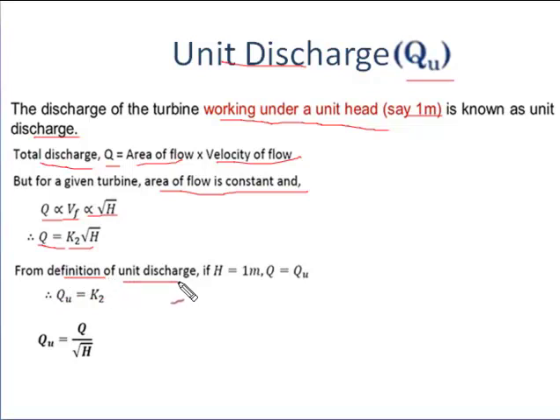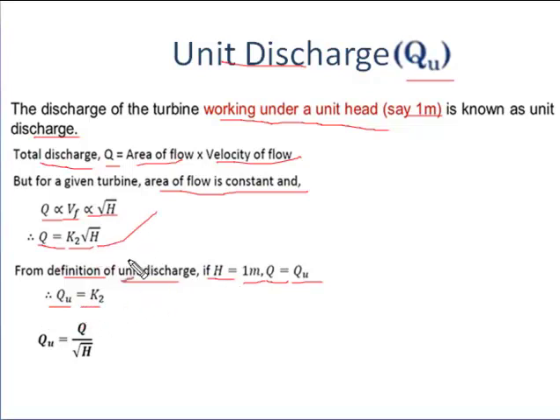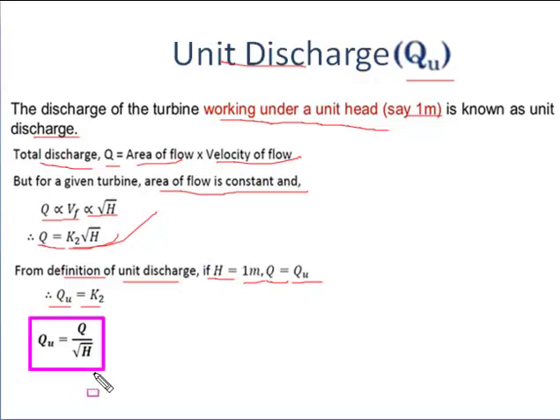Taking the proportionality constant, we get Q = K₂·√H. From the definition of unit discharge, if H = 1 meter then Q equals Q_u. Therefore Q_u = K₂. Substituting this value back, we get Q_u = Q / √H. This equation is known as the unit discharge for the turbine.